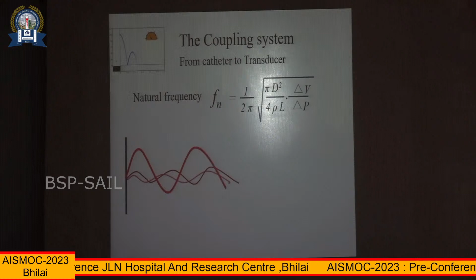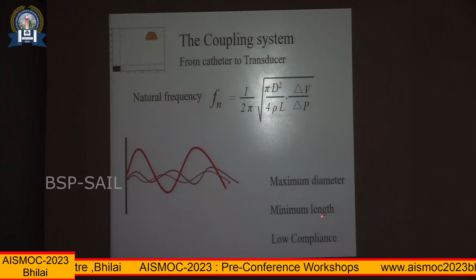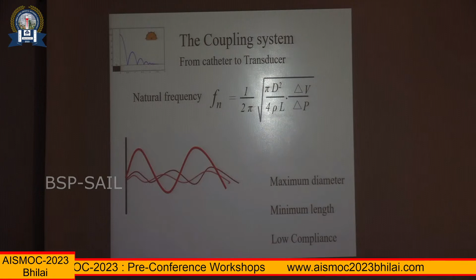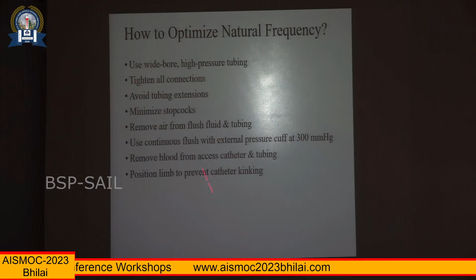Otherwise you will get something called resonance or damping. So you have to have a maximum diameter of the catheter, you have to have a minimum length of the catheter, and you have to have a system that is very stiff or less compliant. Okay, so how do you optimize the natural frequency? You need, like I said, all these things. You need a bigger catheter, shorter length, and so on and so forth.